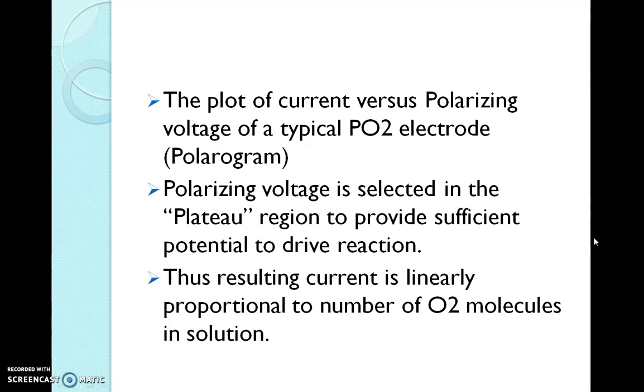When the PO2 level is 0, the current flowing through the circuit is called the background current. Part of the calibration sequence involves setting the PO2 meter to 0 when CO2 and nitrogen gas is bubbled through the specimen chamber. Slow bubbling is used to ensure proper temperature equilibration.